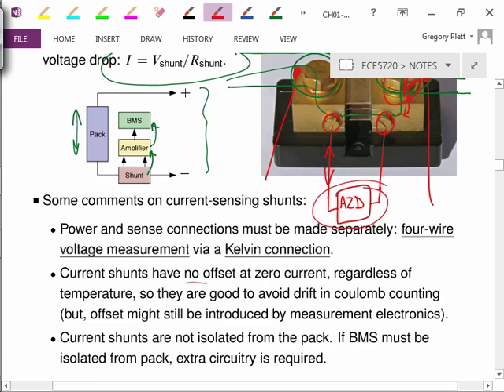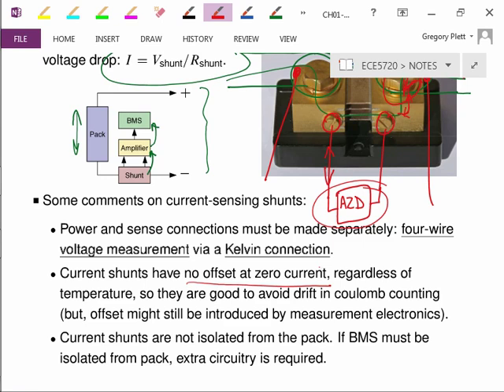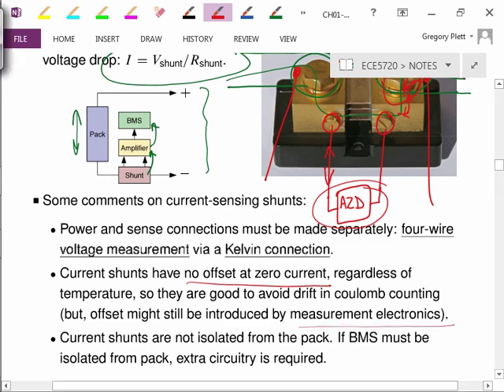Current shunts have no offset at zero current, so the voltage measured when zero current is flowing through is 0. The offset doesn't change with temperature, and that is a very good property. The Hall effect sensor, we will see, can have a bias or an offset at zero current, and that can be a real problem with some battery management algorithms. So if I'm doing something like Coulomb counting, which is integrating current over time to infer a state of charge, it's important not to have any offset. The sensor itself has no offset, but the measurement electronics could have offset, so you have to be sure you are somehow calibrating that out. That's a positive feature of a current shunt versus a Hall effect sensor.